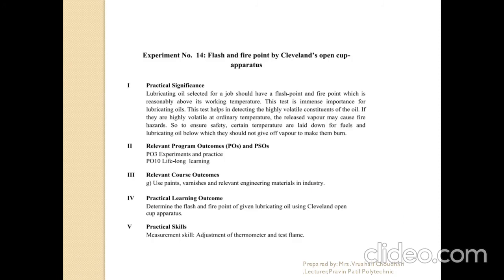What is the flash point? A temperature at which lubricant oil gives a flash is called the flash point. The flash is a flame that lasts less than 5 seconds. If the flame continues for more than 5 seconds, it is called a fire. So we are going to check at what temperature lubricating oils give a flash and fire point.